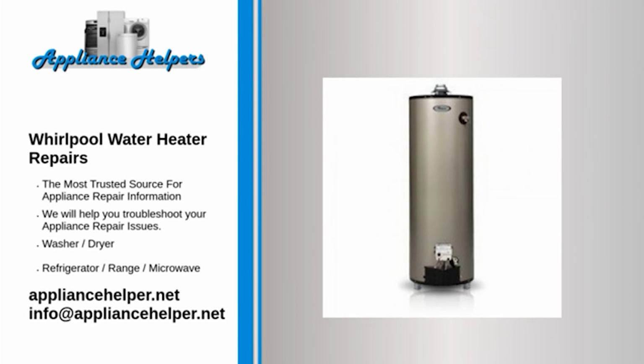No hot water. It may take several hours for a newly installed electric water heater to reach normal operating temperature. If you don't have hot water after 2 hours, or the water is not even warm, first check to make sure the water heater is getting electrical power. Not getting power is a common reason new water heaters don't work.